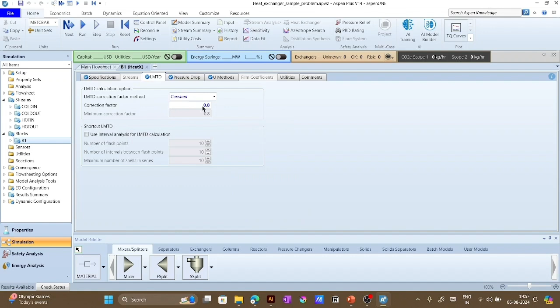In the block part, we have been given that the heat exchanger is operating at 40 kilowatt and an LMTD correction factor of 0.8 is given. So I have specified the exchanger duty as 40 kilowatt, minimum temperature approach as 1 degree centigrade. In the LMTD part, a correction factor of 0.8 is applied. There are other methods also which require different aspects, like geometry, which will calculate based on the geometry of your exchanger. Right now we are using this constant correction factor.